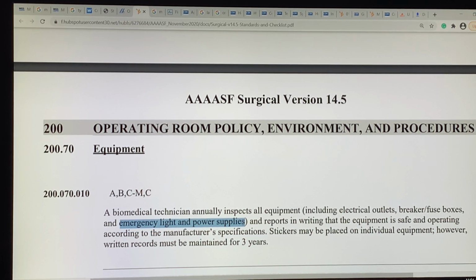So when you install your emergency lighting in the OR, I know it's over the doors, but make sure you also have emergency lighting so that you could finish a procedure. You want that as your safeguard to not have somebody open on the table if something like that happened. The stickers would, like I said, be placed, but the written records, so get a printout. It is time.